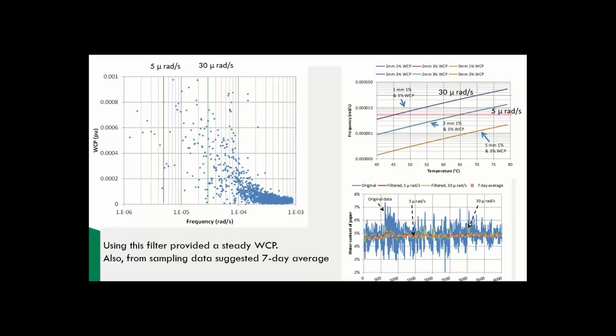So I have here these three graphs. The one on the left is plotting the water content of paper, and we're looking at the frequency content we got from the fast Fourier transform of the signal. Now, on the top right, I took the diffusion time constants of the water diffusing out of oily paper into the oil, and then we can just flip it around into frequency. That's just 1/time, so we're now looking at something which is more like a diffusion frequency constant rather than a diffusion time constant. And what we're now going to say is that if the signal from the water content of paper is changing faster than what the diffusion time constants tell us can happen, then we can filter that out. We can get rid of it.